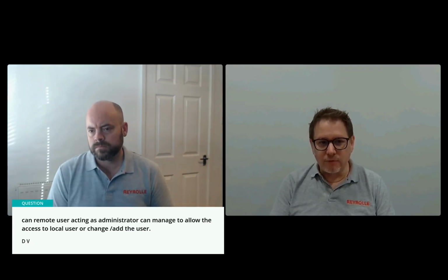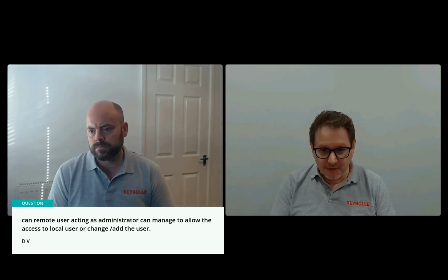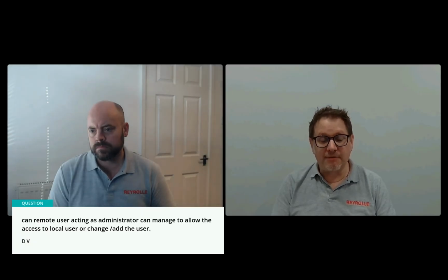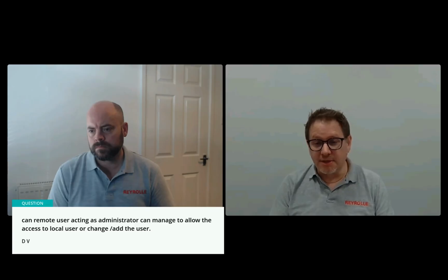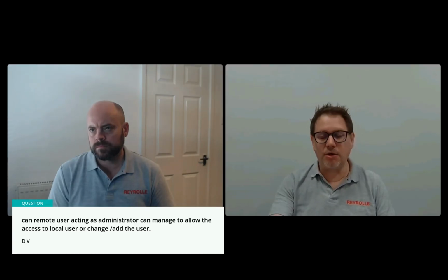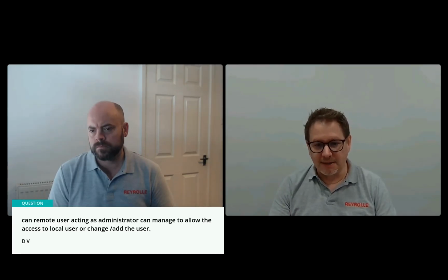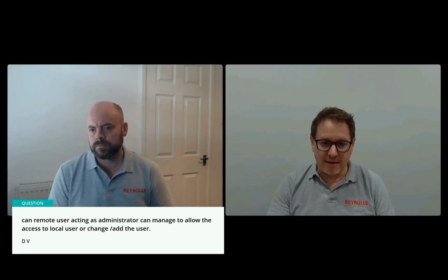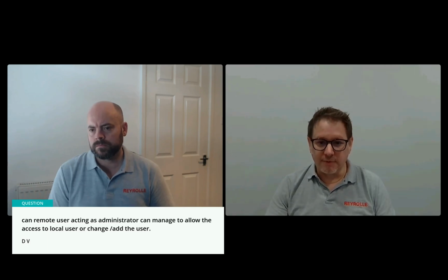If you have that role and privileges of administrator or RBAC management, if you have the correct permissions to update and change the user database, you can do that remotely. You can do it over the front USB, or you can do it over the rear Ethernet. So you would log in, you'd go to the RBAC tile, you could then add or remove users.